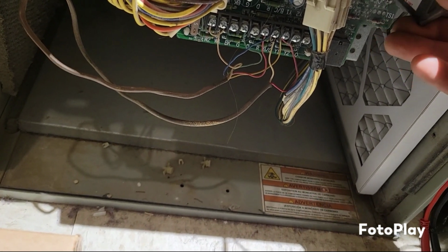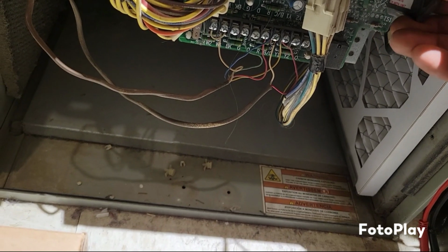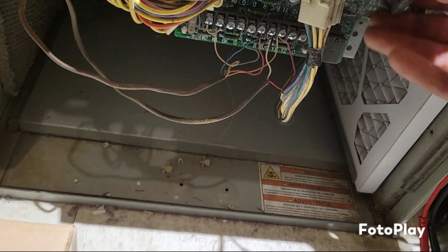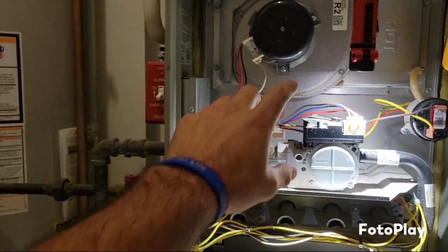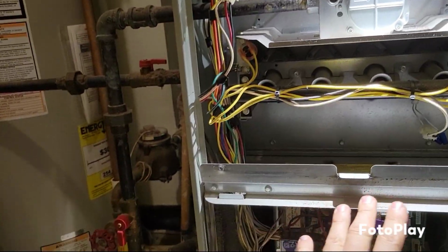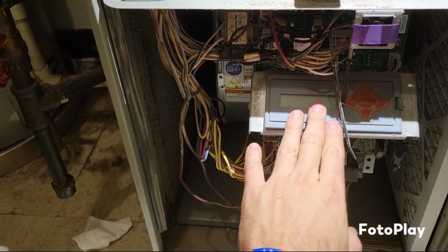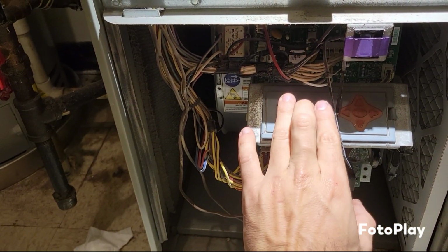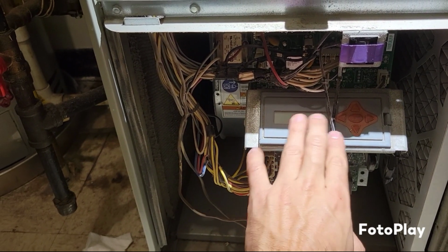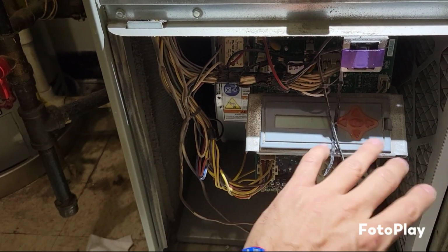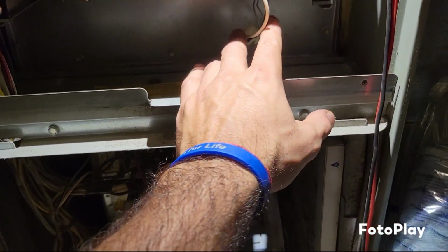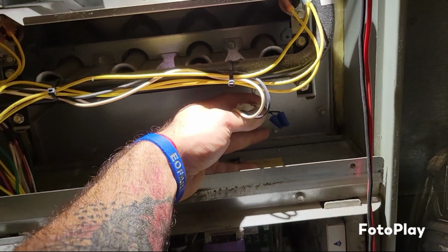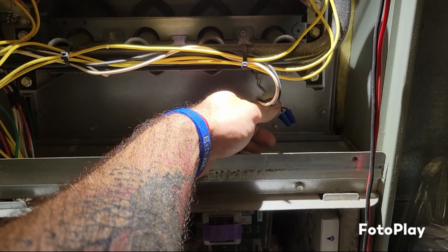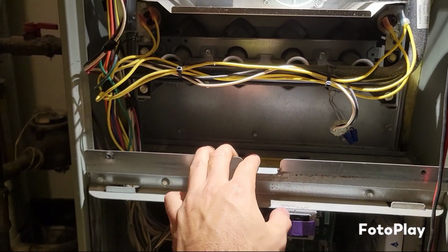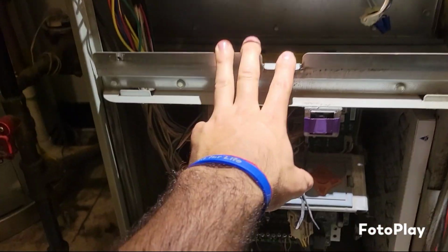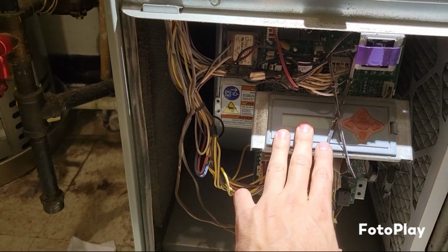Now we're going to be replacing this board, and here's why we're going to be replacing the board. So initially this thing was throwing a bunch of different error codes. There was an error code on this screen right here that showed that the system was not communicating properly with the module. But then we reset the power, restarted everything. You can tell that the igniter has been changed once before. You can see the connectors right there where they made a splice. A couple things have been done to this unit apparently.